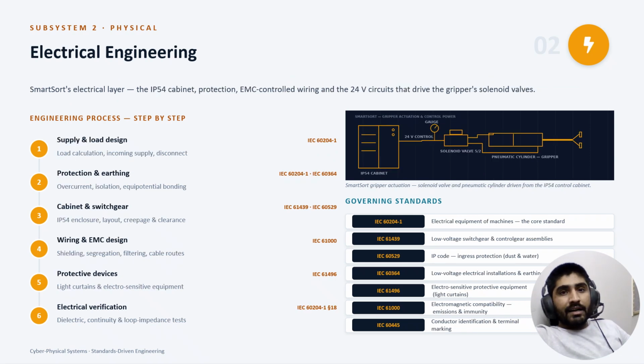Layer 2 of SmartSort: power and its invisible enemy, noise. Look at the illustration. The IP54 cabinet on the left is the heart of this layer, and follow the chain. A 24-volt control signal leaves the cabinet, energizes the solenoid valve, and the valve pours compressed air to the pneumatic cylinder that opens and closes the SmartSort gripper. Electrical control becoming physical grip.